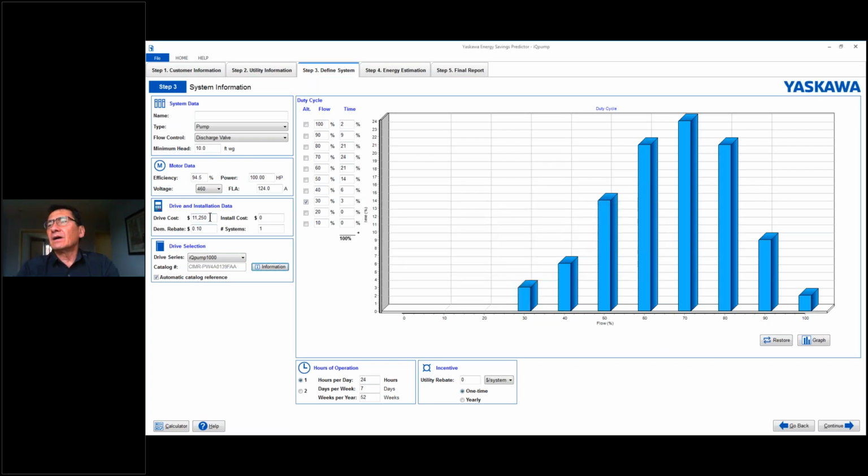So, whatever your drive cost is, now, installed cost, that's what you want to put in here to get a true return on investment, because that's the real dollars that you're spending. So let's say you buy the drive and then you put it in a can, or you buy the drive in a can from Yaskawa in the configured package through Preferred Pump, and that's what Preferred Pump stocks, by the way, is our NEMA 3R configured. And by the time you get all done with that and you basically pour the pad, you drop the box onto the pad, and then you power it up from the power pole transformer, you're going to be into probably close to 3 times this cost. So we're going to put in $33,000.